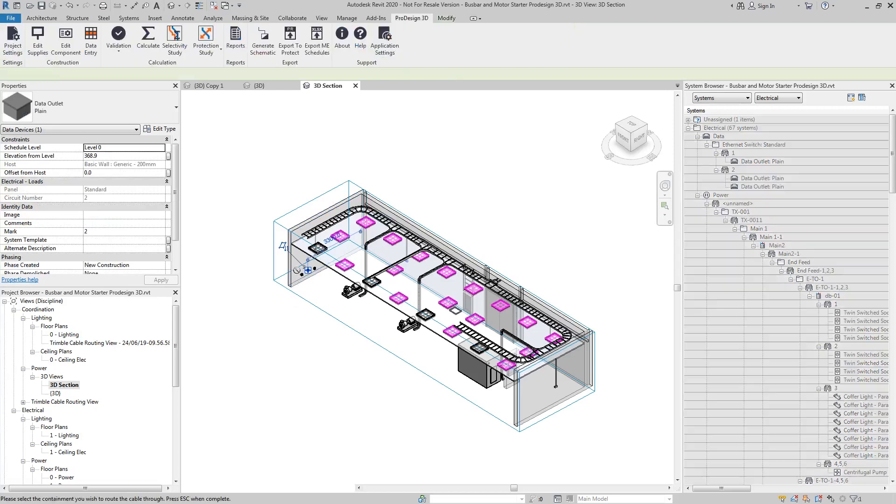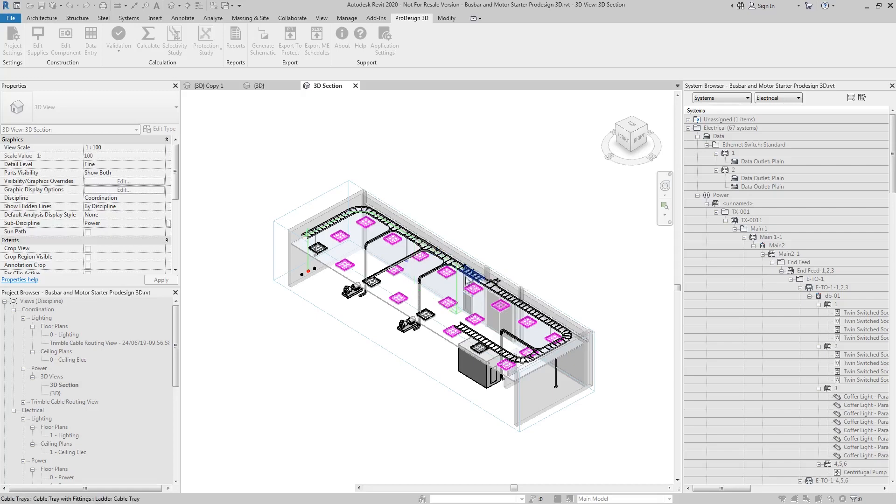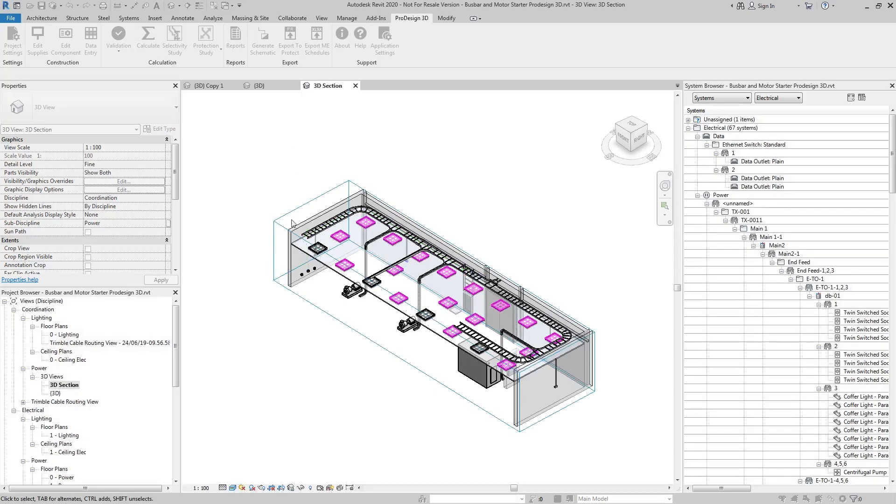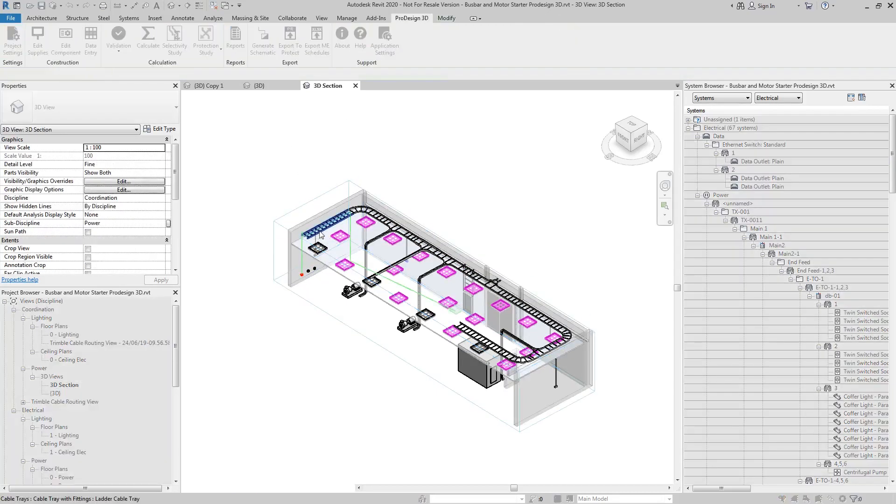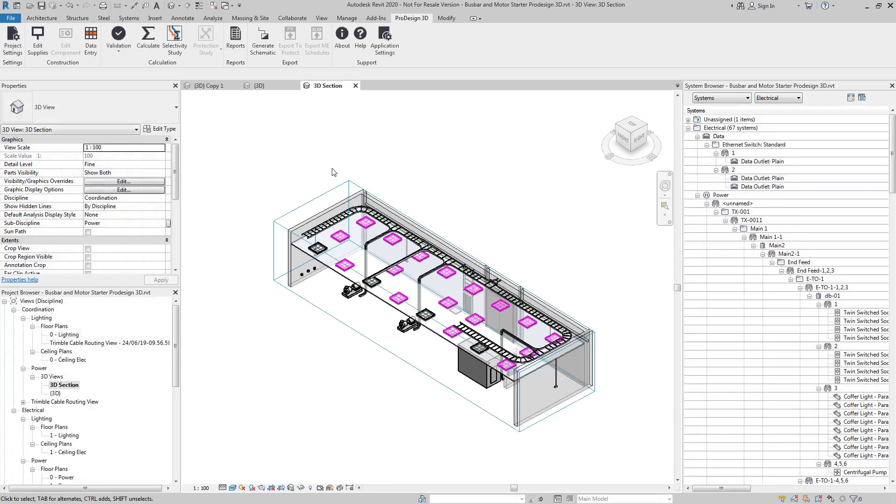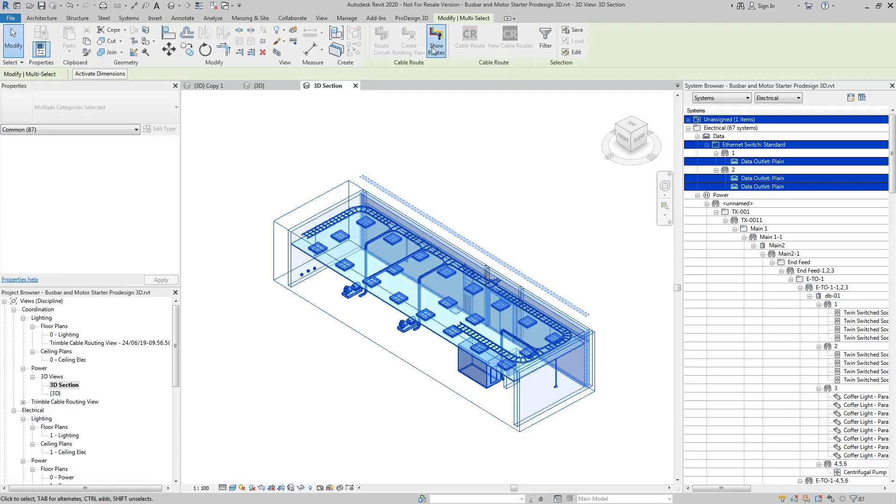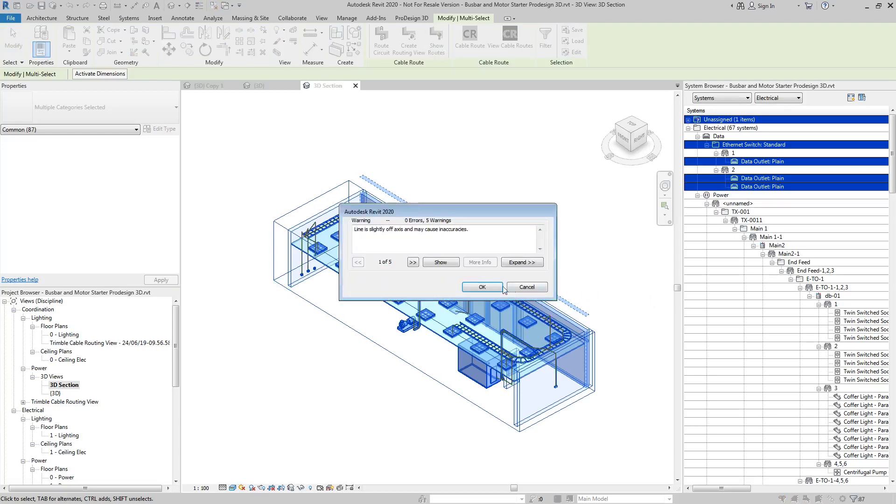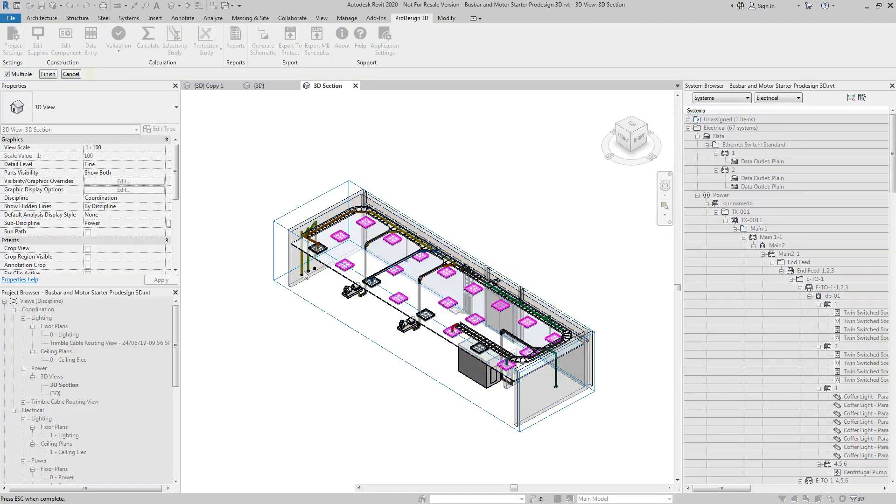We're going to route the path on this one as well. You're going to select the route back to the source. Now you can select every tray component if you want, or you can go to one that's fairly close to where there's a break, select the item, and then that will route it back. At the moment, you can only route one path at a time, which is fine, but it does do what you need to do and it's a lot quicker than trying to do it via Revit's methodology. I'll exit out of that. Just to show the show route again, you can see all the routes populating into the system. As there's more loads, it will run a bit slower. Now you can see all the routes routing back onto the tray and around into the system.